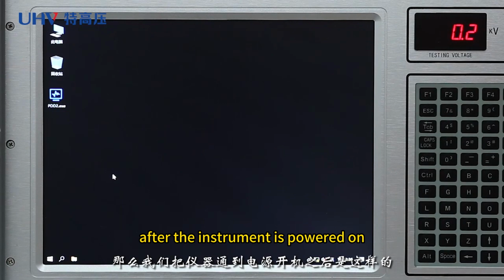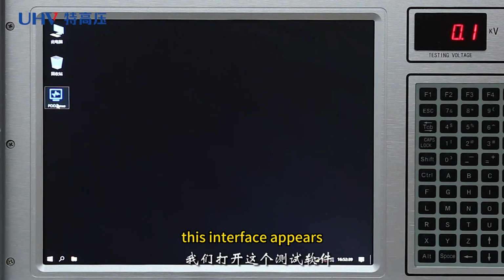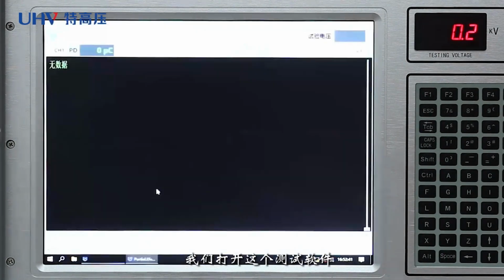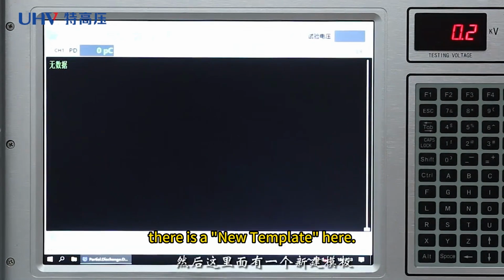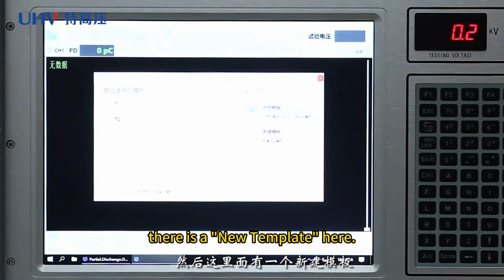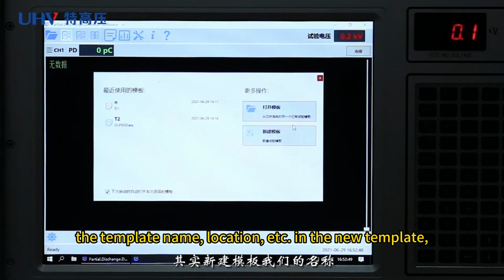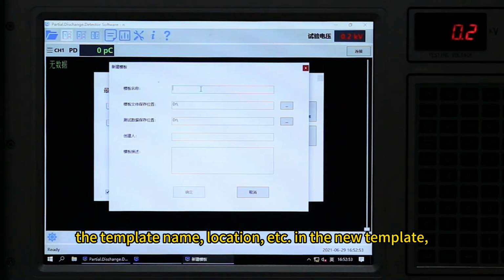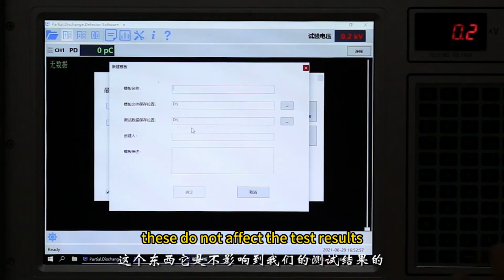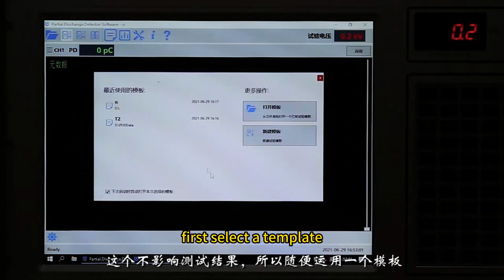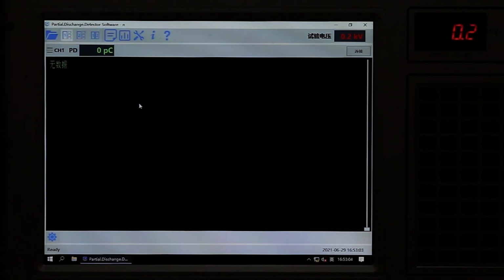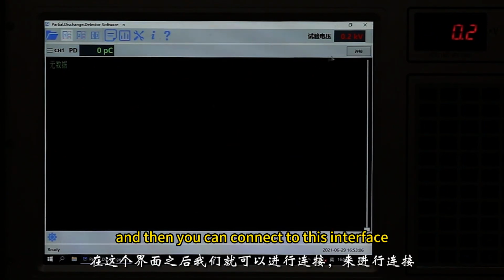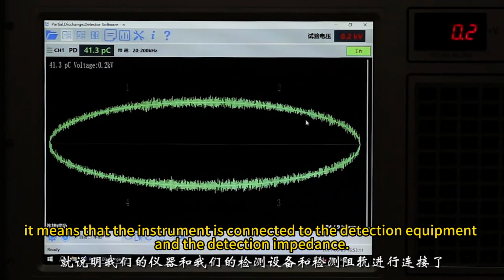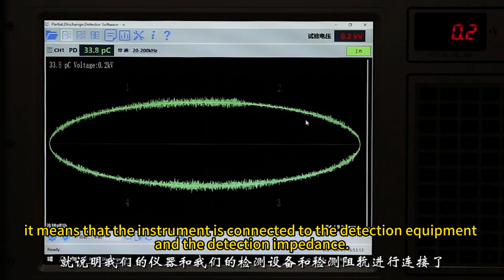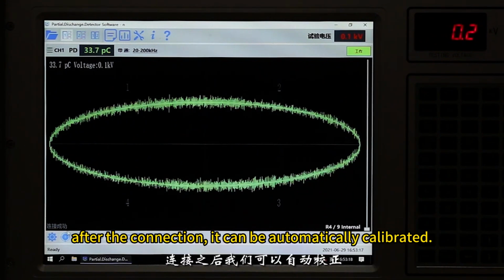After the instrument is powered on, this interface appears. Open the test software. There is a new template here. The template name, location, etc. in the new template do not affect the test results. First select a template. And then you can connect to this interface. It means that the instrument is connected to the detection equipment and the detection impedance. After the connection, it can be automatically calibrated.